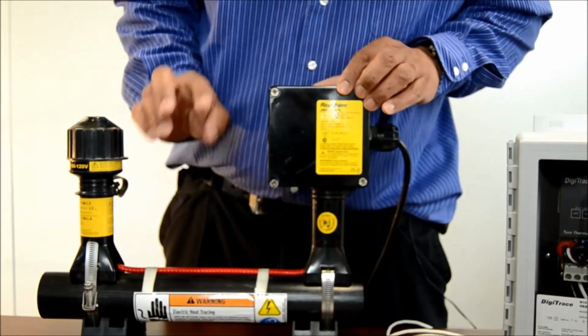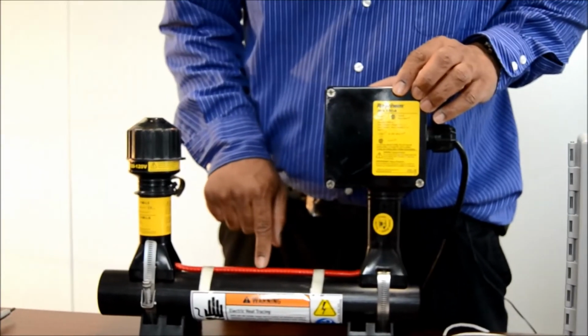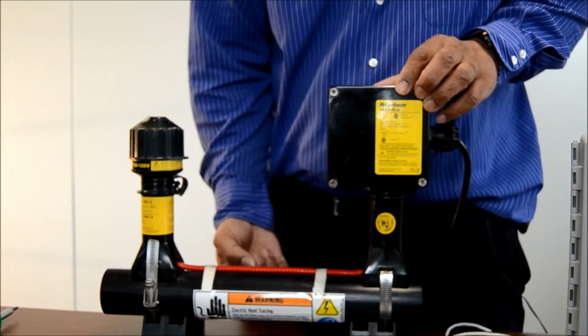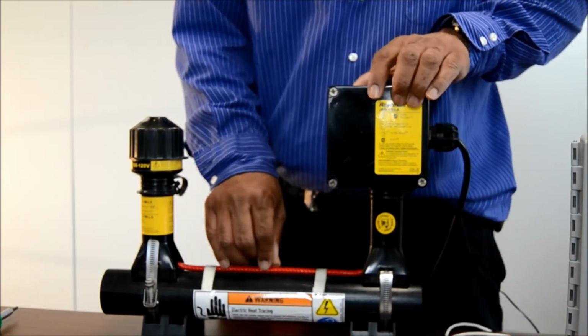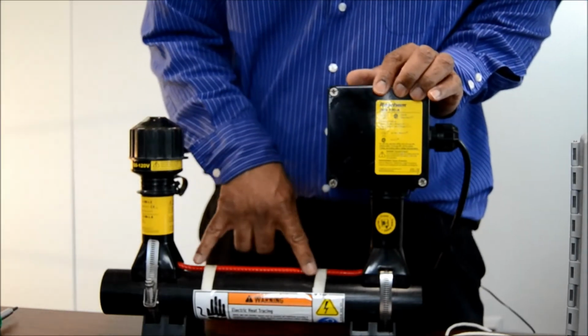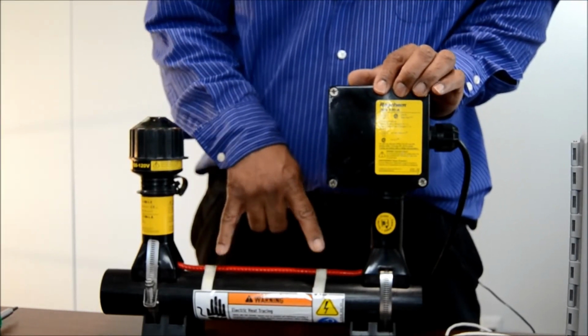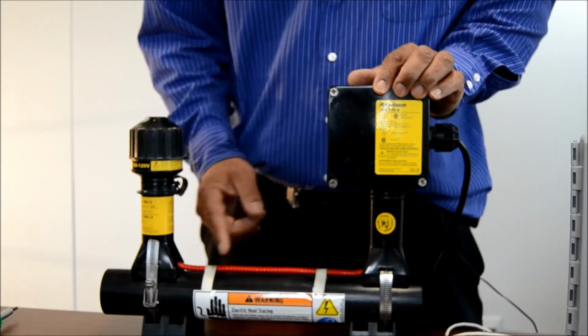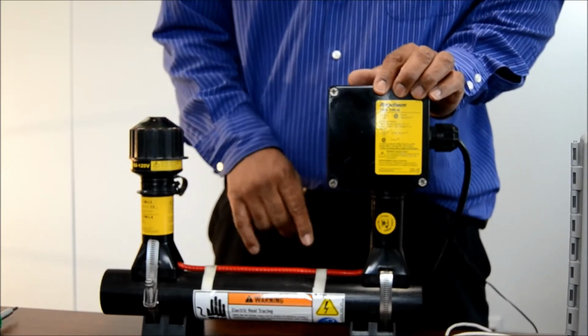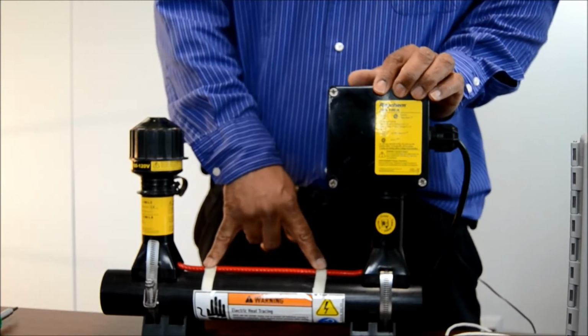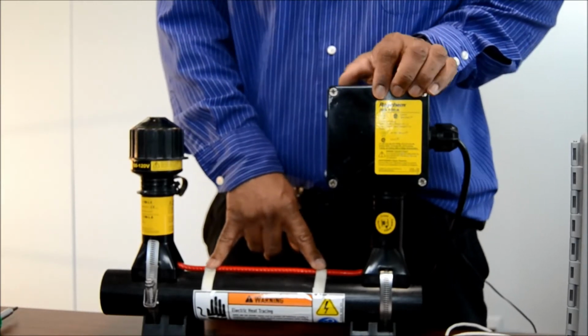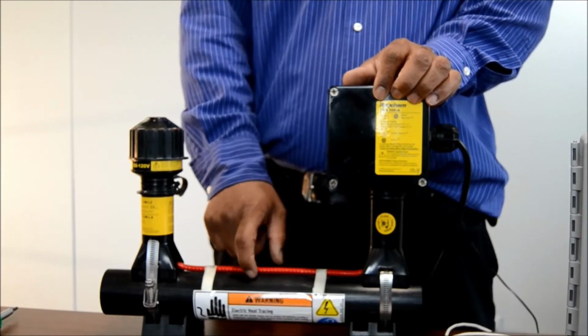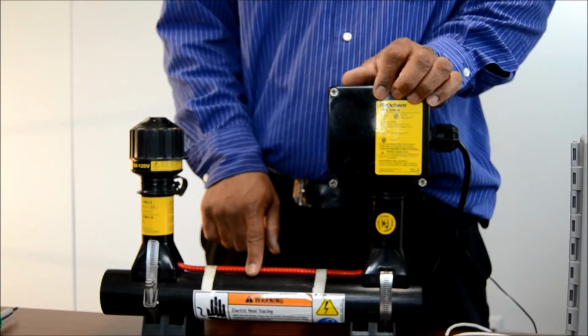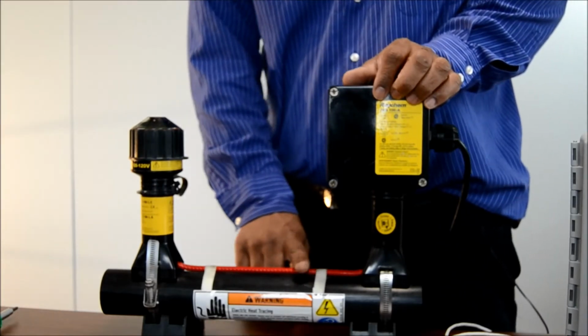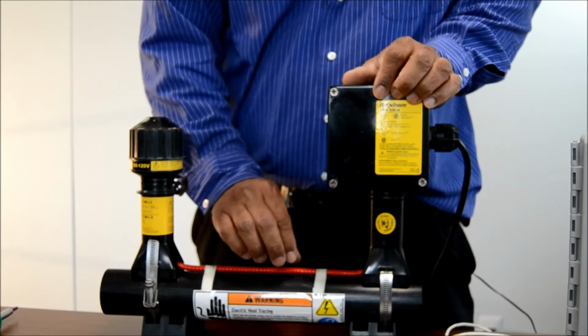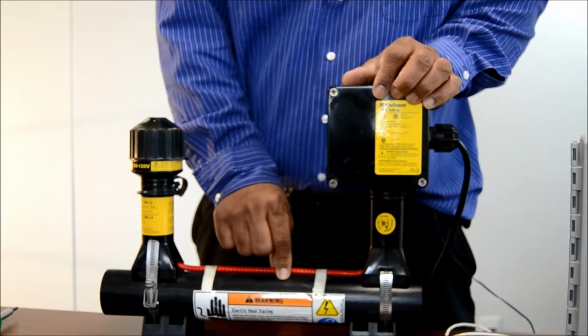Now this demo is a little incorrect because usually you'll have the heat trace at either 4 or 6 o'clock on the pipe itself. Also, you mount the heat trace with either glass tape if you're using steel, and the glass tape comes in two different types. One is a GT66 and one is a GS54. If you're using this on PVC or fiberglass pipe or stainless steel, you want to use an aluminum tape that goes across the heat trace, and it attaches the heat trace to the actual pipe.